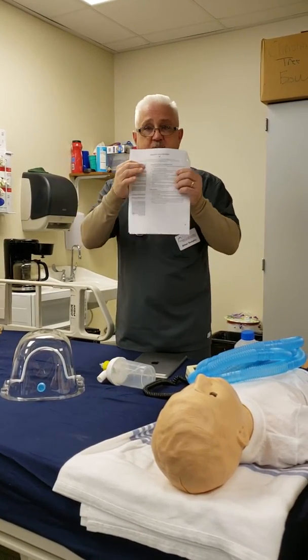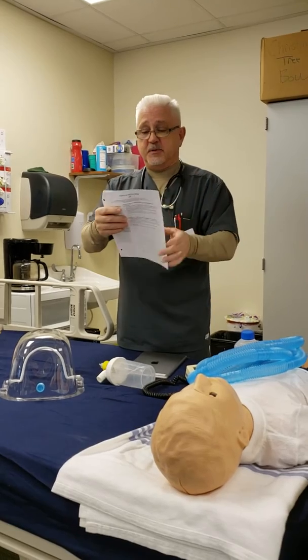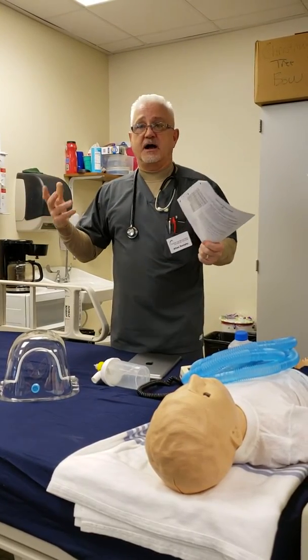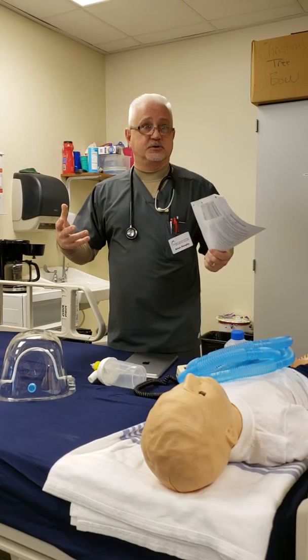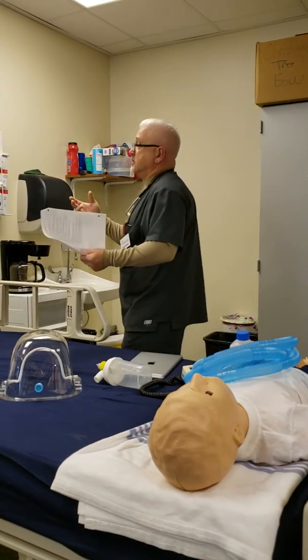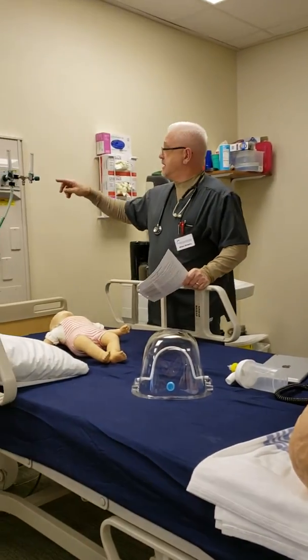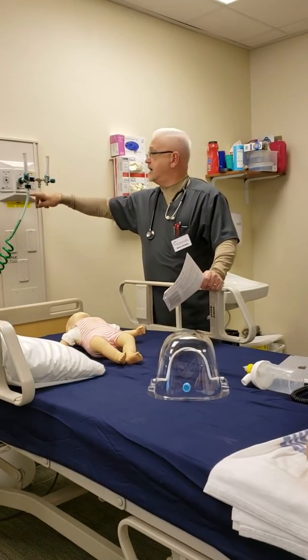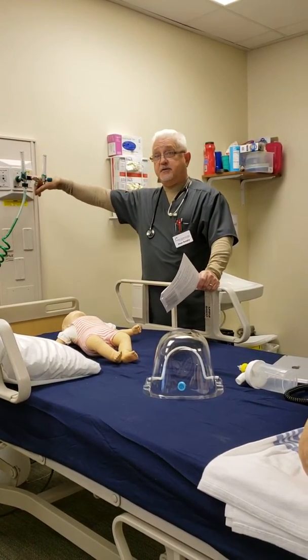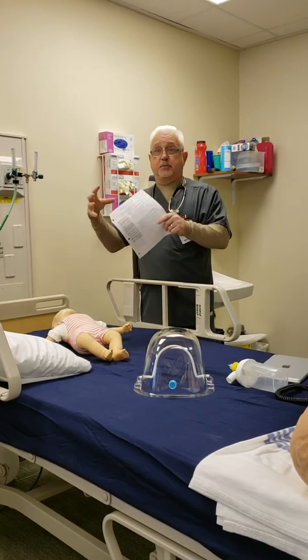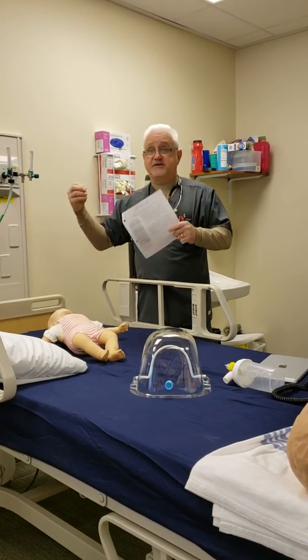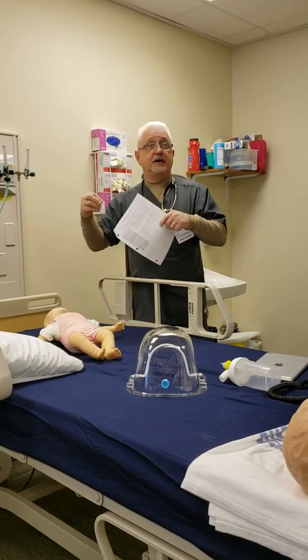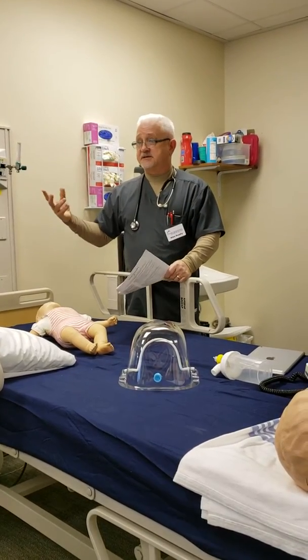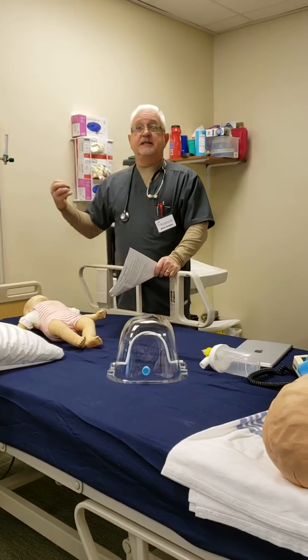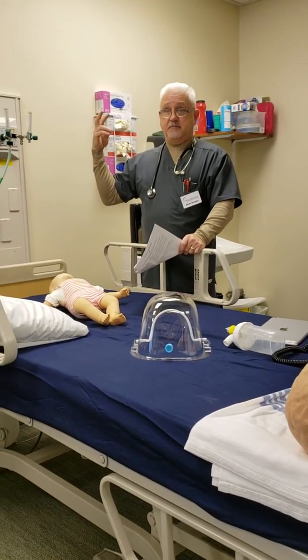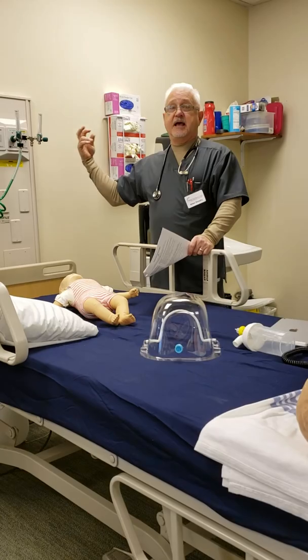It says implementation of the procedure, and the implementation of the procedure is that you're going to make sure that your oxygen blender is connected to your sources. With an oxygen blender, you have to use two high pressure sources, air at 50 psi and oxygen at 50 psi. Both of those high pressure lines plug into your blender. If both of those sources are not plugged into the blender, it's going to make an alarming sound. That's showing you that you don't have the two medical gases required at the proper pressure level.